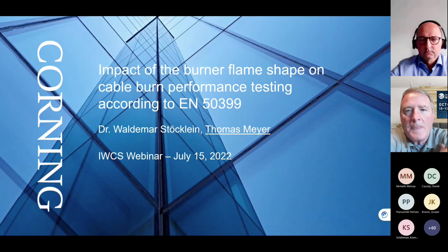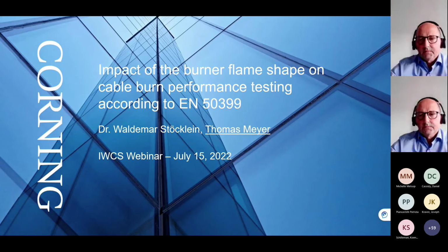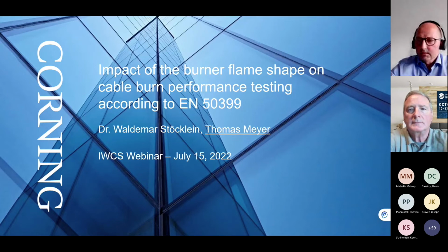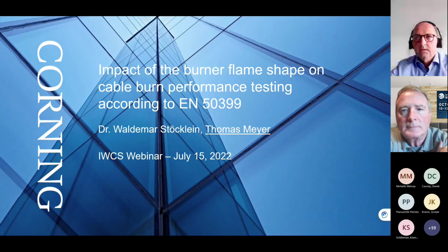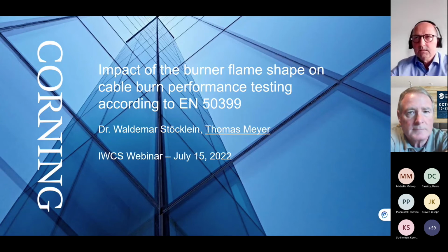Okay, are there efforts to verify correct flame shapes at different labs to ensure repeatable results? To me it's quite important that if the new standard is published, laboratories will be following this method. The method is informative, but I would strongly recommend to do it, and not just once per year.